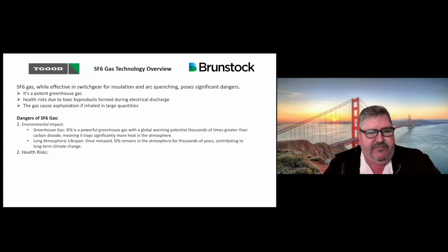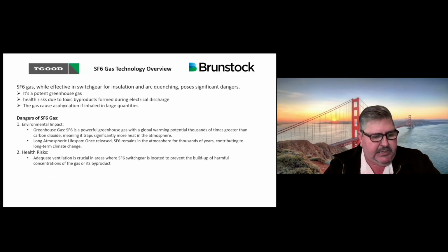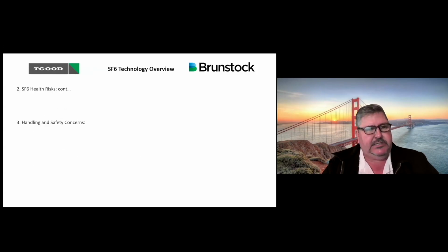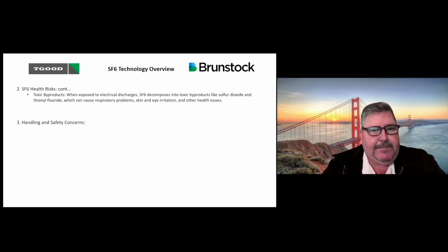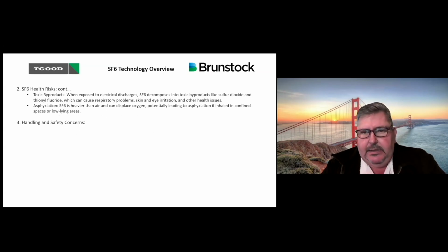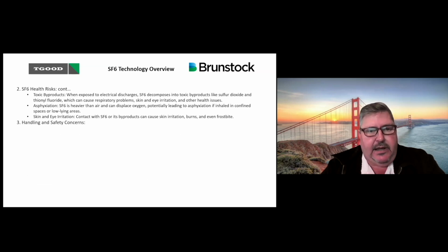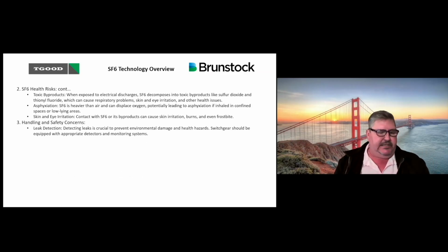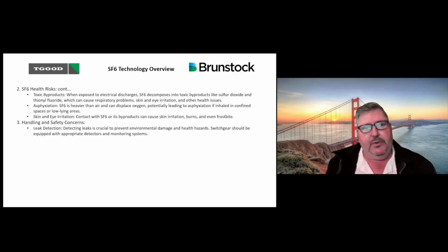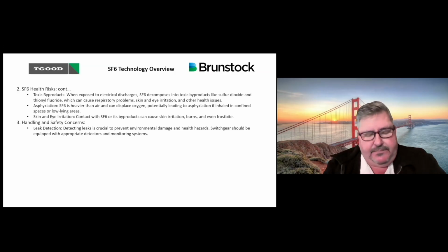It also poses a very big health risk, so ventilation is crucial where the gas is exposed to the atmosphere. The risks continue, and it could cause asphyxiation due to exposure to the product. It can also cause skin and eye irritation, and even frostbite. So for handling safety, it is very important that leakage detection is available when you do use SF6 gas.